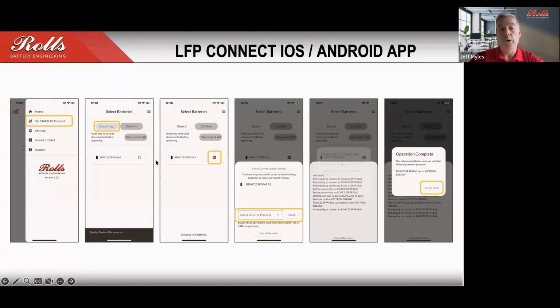One thing to note though is that if you do reassemble the batteries in a stack again, you would need to reset the dip switches according to battery 1, 2, 3, and 4 in the order of the stack. So whether the protocol is assigned to it or not, you would still have to complete that step in order for the batteries to be connected properly.